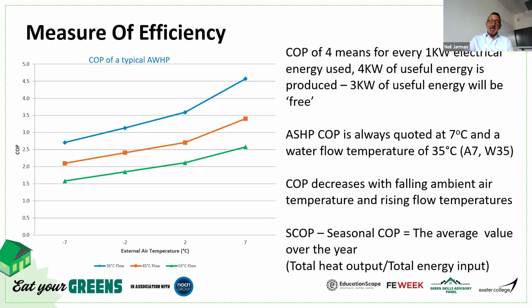All right. COPs, they don't really say what's on the tin. Your best option really is to work your SCOP out, which is the seasonal COP. And that's done by dividing the total heat output by the total energy input, okay, over a 12-month period.